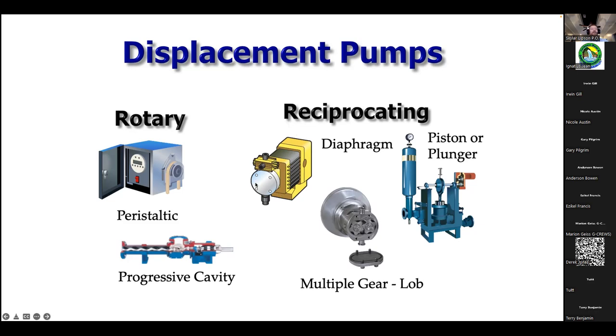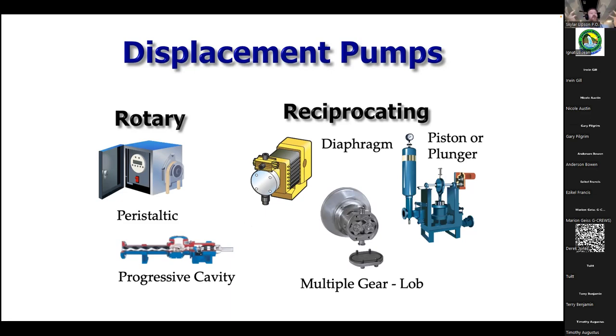A diaphragm pump has a flexible diaphragm with a rod attached. As the rod pulls back it draws fluid into the created space. Through two check valves — one on top and one on bottom — fluid is drawn in and then pushed out. This pump generally has two controls: speed, which is how fast it moves, and stroke, which is how far the rod pulls back on the elastomer diaphragm before returning to the pump cycle.